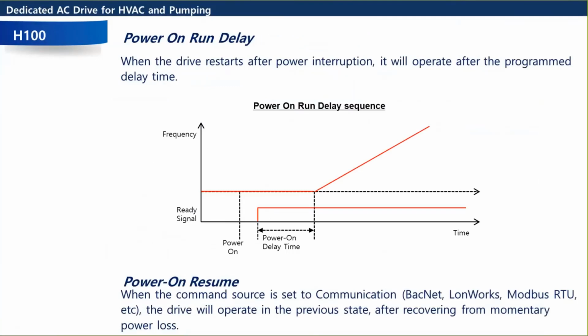And then we have the power on run delay. This is good because if we ever have a power interruption, after a momentary power loss, all the loads come on together, right? Everything connected to the utility is going to try to start up. So it might be a good idea to put a power on run delay, so that you're not coming on with everything else. You can wait 5 seconds, 10 seconds, whatever you need to do, and then after the line stabilizes, not all that inrush from everybody else jumping on the line, then you're okay to run the drive. This might be especially useful if you're running like a 600 horsepower motor. So, no big deal to wait an extra 10 or 20 seconds.